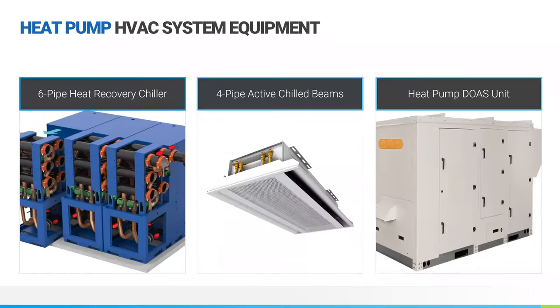So the HVAC equipment actually used in the building, one of them was known as a heat recovery chiller. You'll see there it's got six different pipes. One set of pipes is for what is known as the source, which would be in this case the wastewater energy recovery system. One is the hot water loop and then the other is the chilled water loop. Those hot water and chilled water loops are supplying what's next to it, known as a chilled beam. So don't let the name fool you. It says chilled, but it can also provide heating.